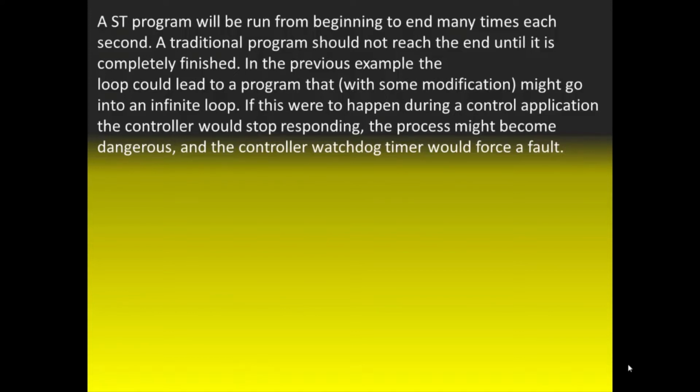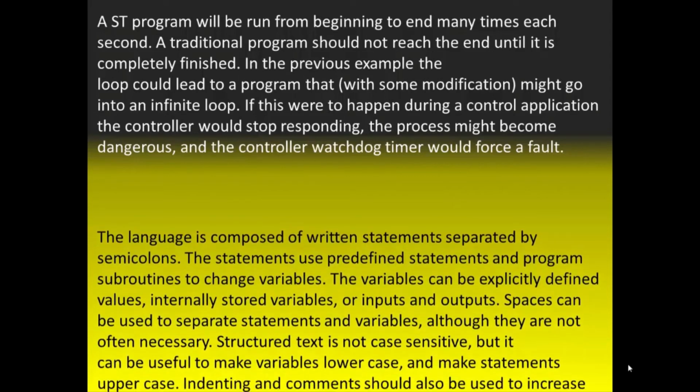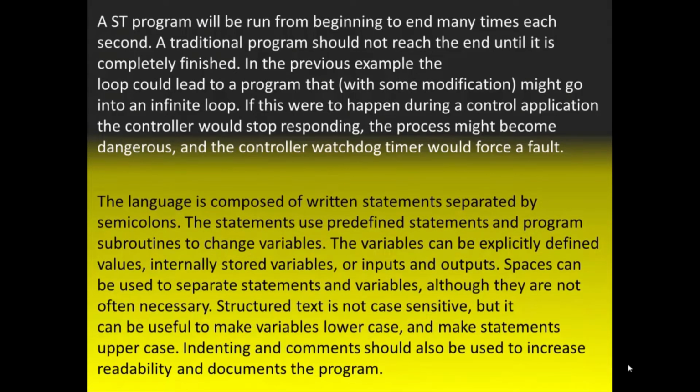If this were to happen during a control application, the controller would stop responding. You'd have a watchdog timeout. The process might become dangerous and the controller watchdog timer would force a fault. The language is composed of written statements separated by semicolons. So you could say that the rungs of logic are separated by semicolons. The statements use predefined statements and program subroutines to change variables. The variables can be explicitly defined values, internally stored variables, or inputs and outputs.